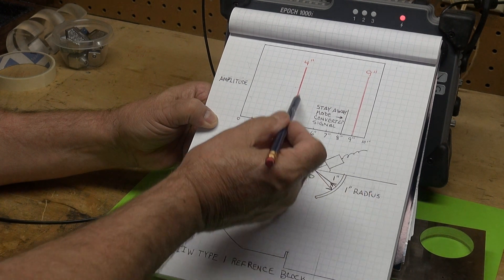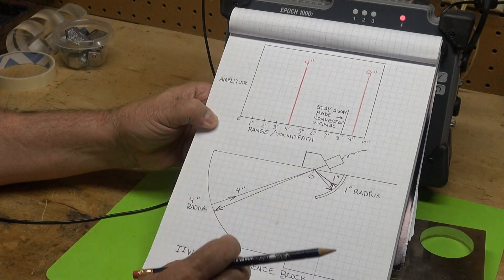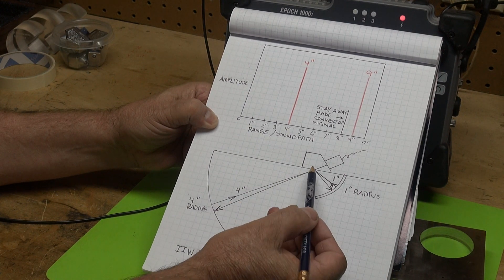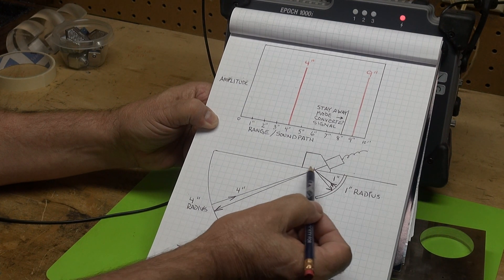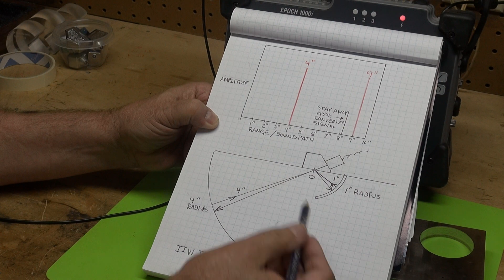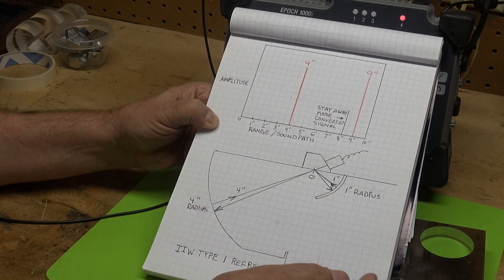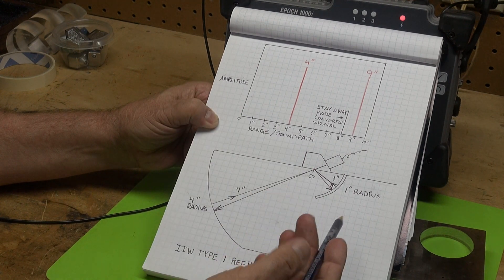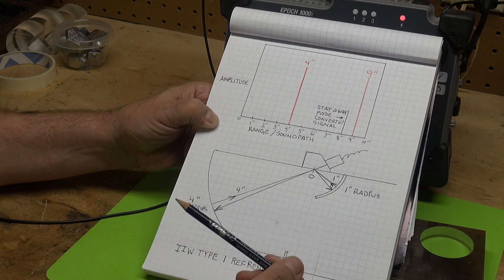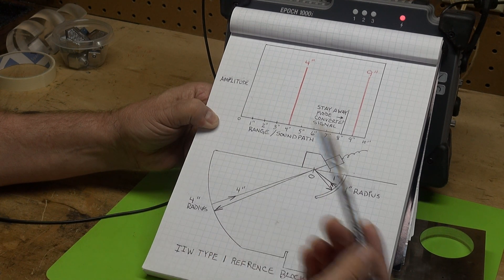Therefore it records that reflection. I know some of you are saying that's 8 inches of sound path. That's correct, but measured is 4 inches. I'm assuming that the electronics inside of our ultrasonic testers does a divide by 2.